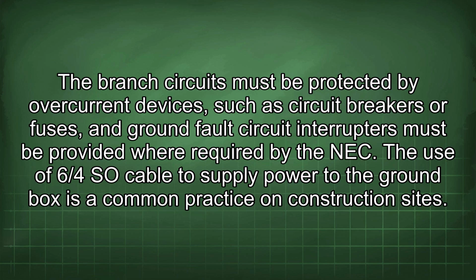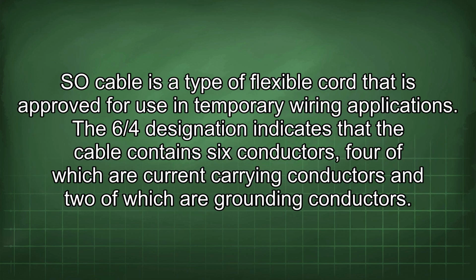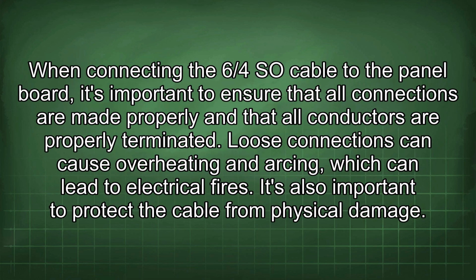The use of 6/4 SO cable to supply power to the ground box is a common practice on construction sites. SO cable is a type of flexible cord that is approved for use in temporary wiring applications. The 6/4 designation indicates that the cable contains 6 conductors, 4 of which are current-carrying conductors and 2 of which are grounding conductors. When connecting the 6/4 SO cable to the panel board, it's important to ensure that all connections are made properly and that all conductors are properly terminated. Loose connections can cause overheating and arcing, which can lead to electrical fires.